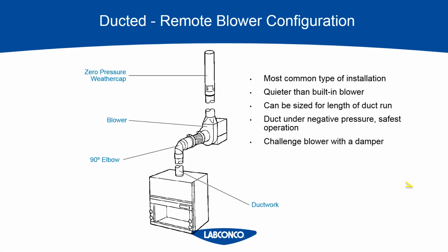Then that means that the fan either changes RPM or there are valves in the system that talk to each other and keep the supply and the exhaust air in the room in balance. One blower can operate more than one fume hood on this type of configuration, and that's kind of the beauty of it. You can size the blower for whatever the hood and the duct run need. The reason this is the most popular installation is because all of the ductwork is kept under negative pressure. Meaning if you were to get a leak in the duct run between the hood and the blower, and let's say that ductwork goes through an office space, something that has nothing to do with what's going on inside the hood, then the fan will just suck air in through the leak, not allowing the harmful vapors out of the leak.